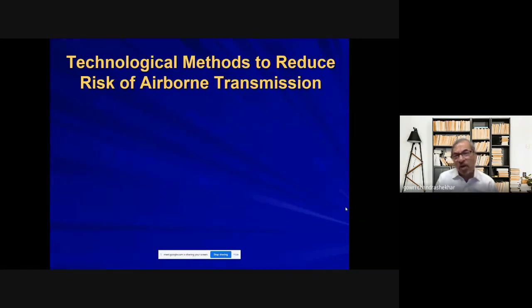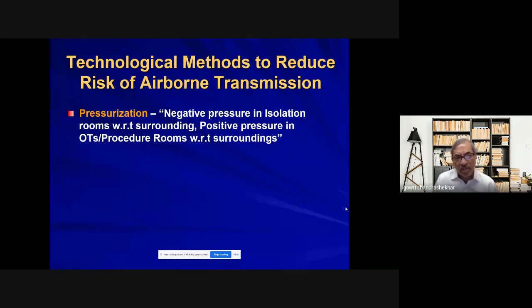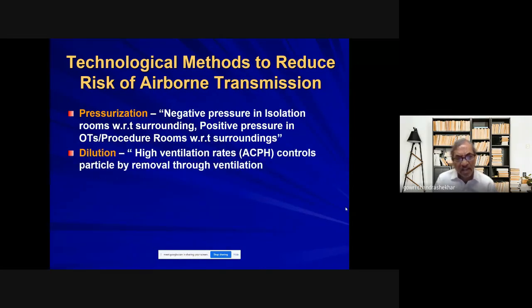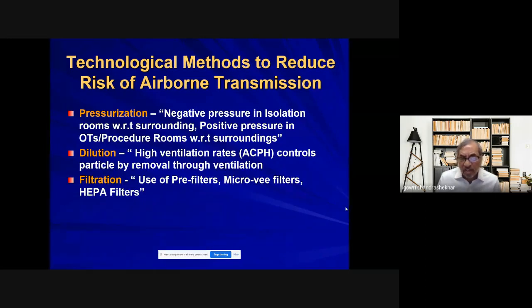So, technological methods to reduce the risk of airborne transmission. We always used to use three methods. Now I am going to tell you the fourth method, which I always used to insist on but was never given importance - COVID has made it mandatory. The first is pressurization, where everybody is aware about negative pressure in isolation rooms and positive pressure in OTs, etc. Then dilution means more high ventilation rate, that is air changes per hour, to control particles by removal through ventilation. Third was filtration, using a pre-filter, Micro-Vee filter, HEPA filter, etc.